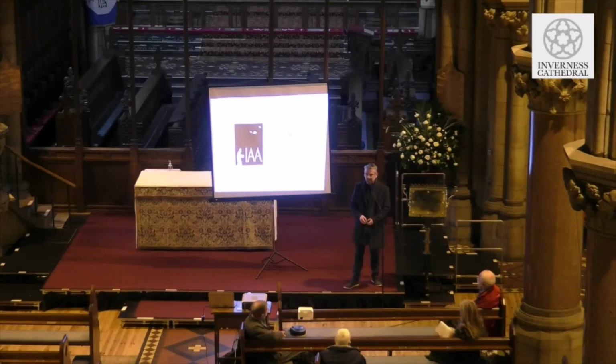So air tightness, coming back to, I can't remember the figure you quoted, 11 or something. I would have said that was pretty good for a traditionally built building. I would have thought that was quite low. Generally, for people's general health, you want 1.5 air changes per hour in the building. In a lot of traditional buildings, it may be 10, 15 air changes an hour, depending on when it was built and how well it was built and how well it's been maintained. So when you suddenly do a retrofit and all this ventilation drops, it's going to have a dramatic effect, and it needs to be managed carefully.